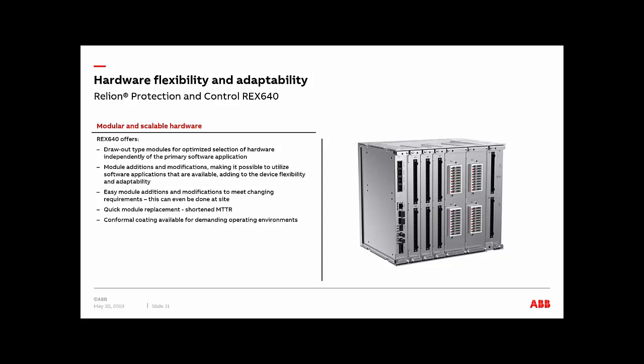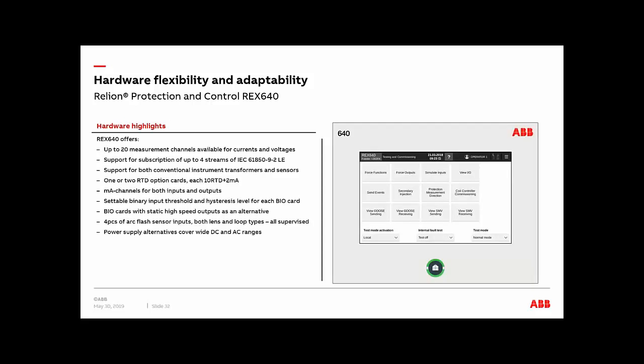You also have the option of having conformal coating, which is available on this relay as well if you order it at the time of purchase. Some of the main things on the hardware: we have up to 20 measurement channels available for current and voltages. We have subscription for up to 4 streams of IEC 61850. We mentioned also that you have the option of having traditional current and voltage transformers, or you can have current and voltage sensors available on the relay, or you can have a combination of those as well and do the same that you would do with traditional CTs and PTs. So you have 1 or 2 RTD option cards. Each of them has 10 RTDs and 2 milliamp inputs, and outputs as well. So you've got milliamp channels for both inputs and outputs.